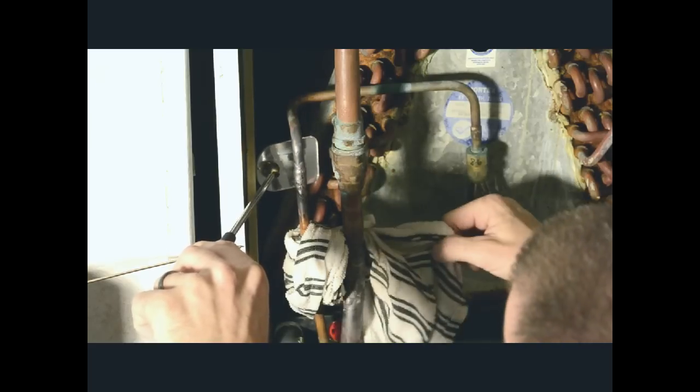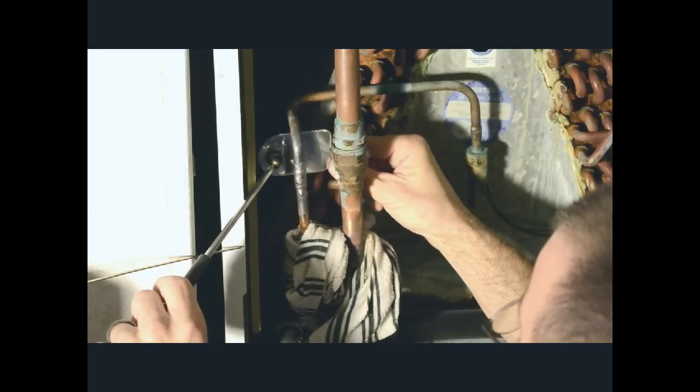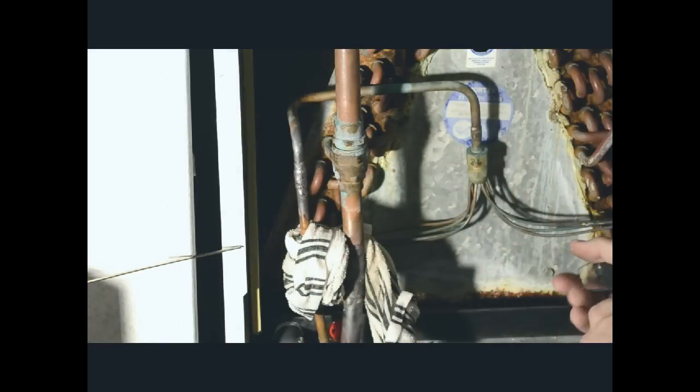At this point Mike has already welded the first and he is attempting to weld the second one. We have the first coupling done down here, hopefully ugly welds, and I'm checking the second one to see if I have any obvious spots that I've missed on the solder. My mirror is not cooperating. These little plate mirrors they scratch up so easy. We will put a little nitrogen in it and mix up some soap bubbles real quick cause I forgot to do that earlier and we will test to see if we have any leaks. Hopefully we won't have to do any more welding.